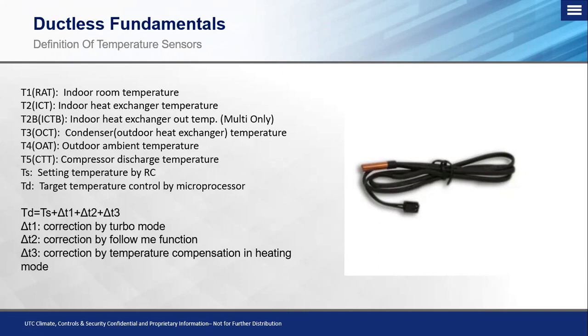Now we look at the multi-zones, you'll notice there's a T2B. Now what this is, is an outlet temperature sensor of the EXV. The EXV is on the outlet side, and we'll just use the cooling mode as an example. We need to figure out what temperature after we create that pressure drop or that change of state from liquid refrigerant to a mixed phase refrigerant. We need to monitor that temperature to make sure that that valve is set in the correct position. And this is what this T2B sensor looks at. Now on the multi-zones, you're going to have one for port A, port B, port C, etc., depending on how many ports you're actively using.